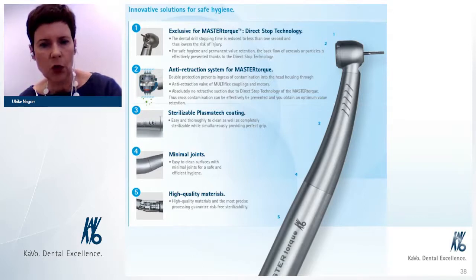In addition to that, the coupler, the multiflex coupling, the fast coupler, also does have an anti-retraction valve. So even in use of an older turbine version, we protect as much as possible the treatment unit from a recontamination out of the contaminated aerosol cloud. All KaVo instruments do have surfaces which provide a safe and easy grip, but also allow to perform hygiene maintenance. In our premium instruments, we have this specific Plasmatech coating, metal ceramic coating, which is very easy to brush, to clean from any residues of materials after use.